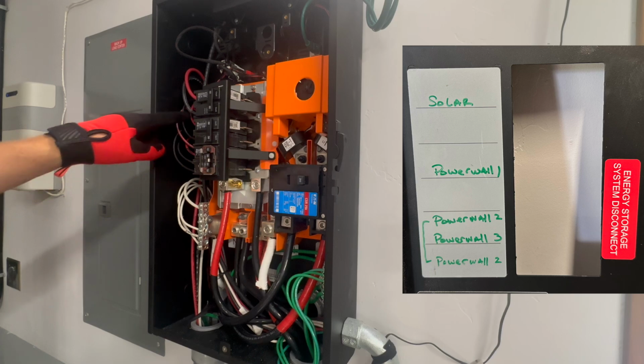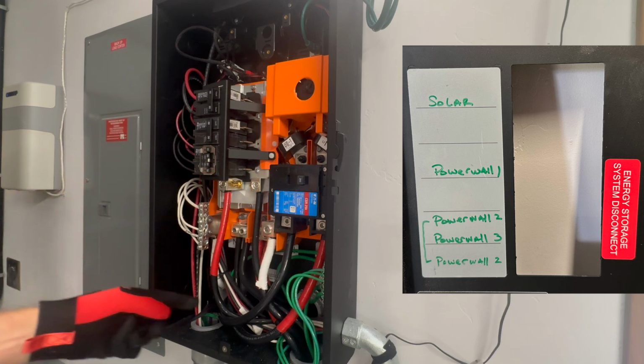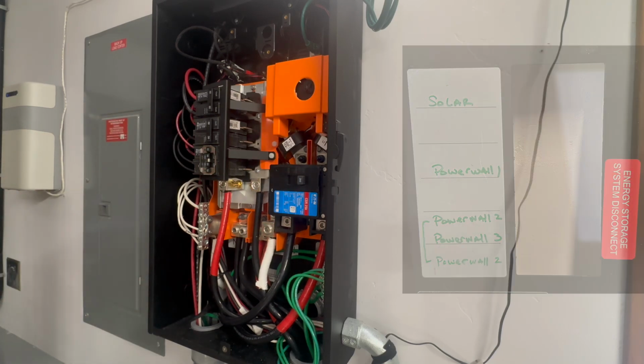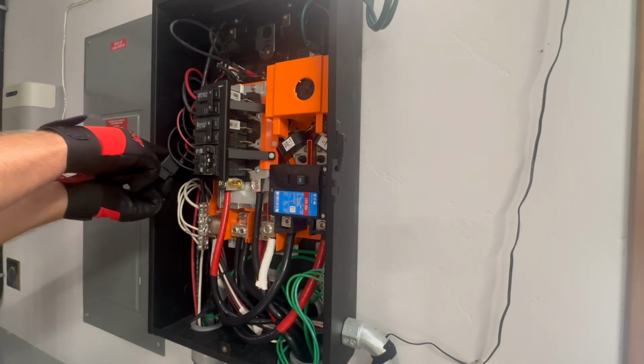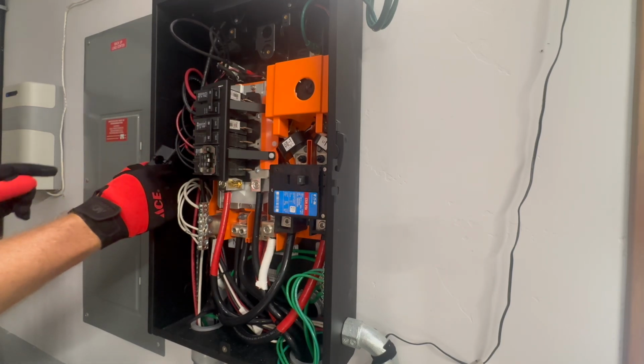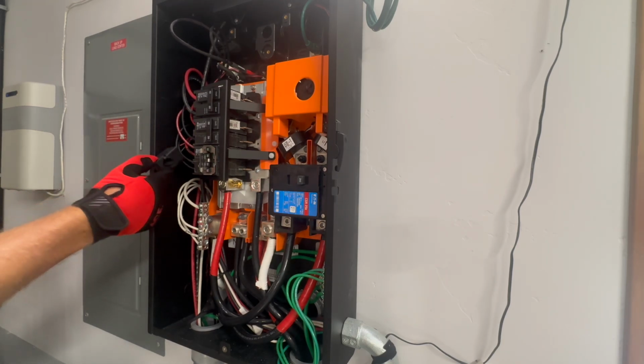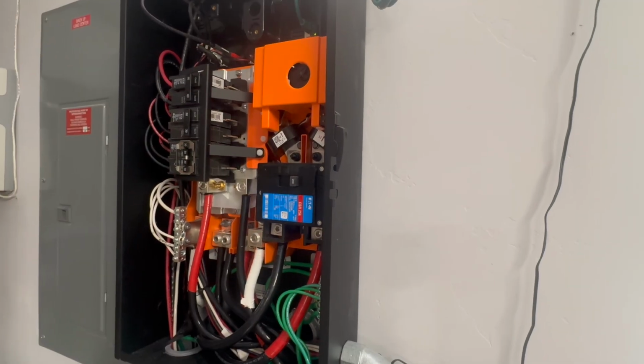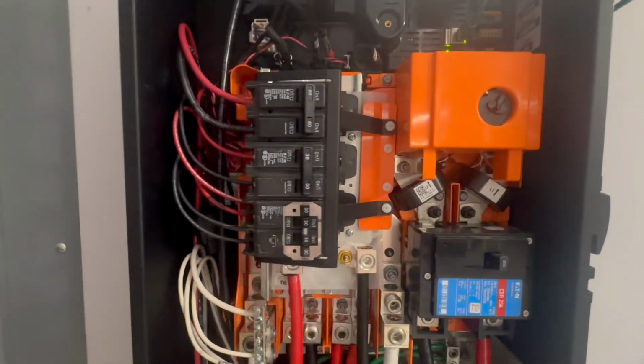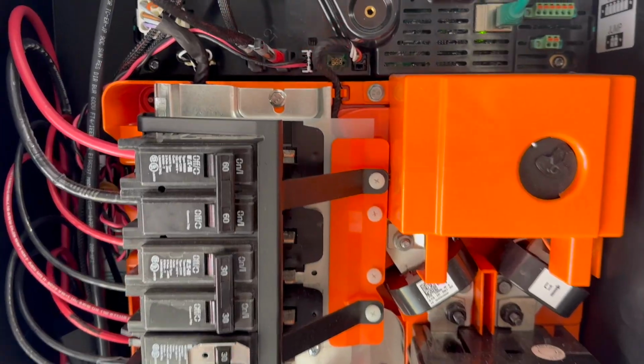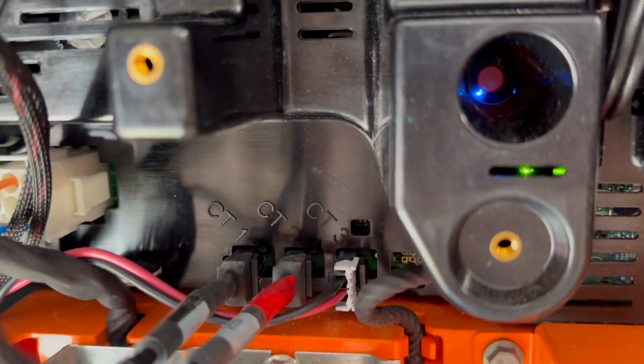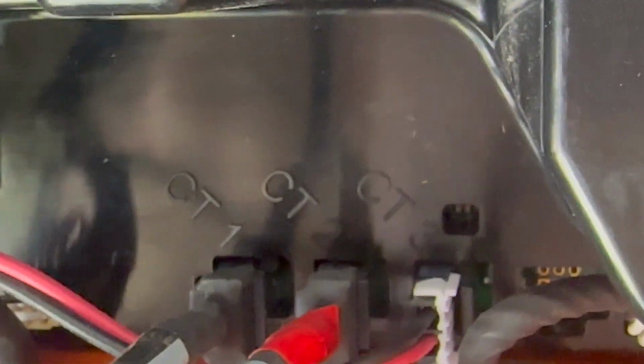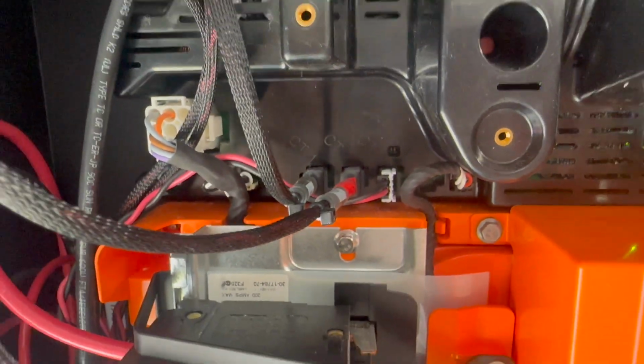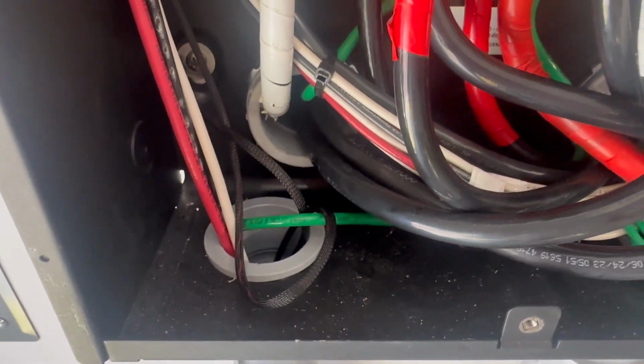Okay, so this breaker bank on the left is where all the backup power comes into the system. I noticed nestled away back here that there was at least one CT that isn't clipped around any wire at all, but it does plug in up here into this connector marked CT3. Obviously that has nothing to do with the EV charger, since the EV charger was being metered, just backwards. So the EV charger must be metered by the two CTs that plug into CT1 and CT2.